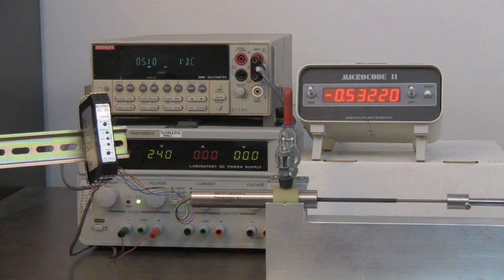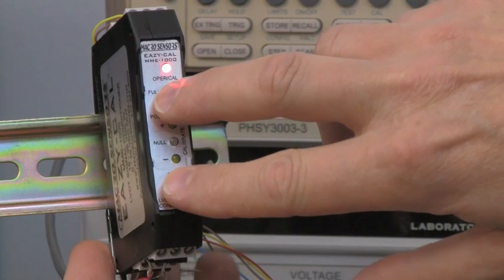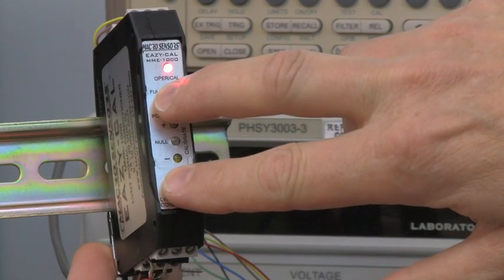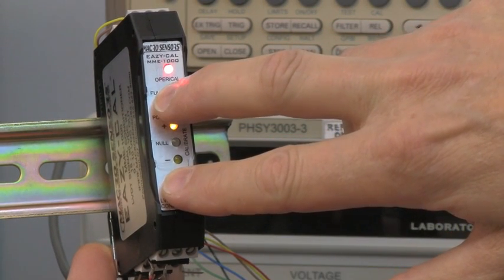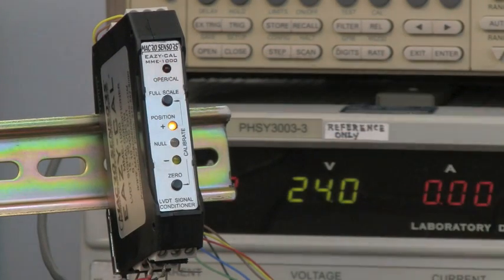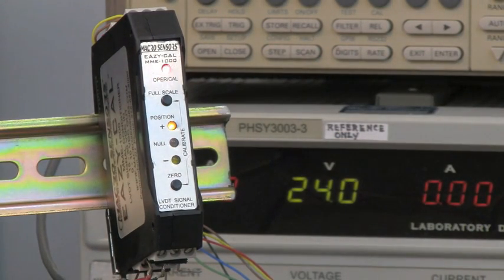With the EAZY-CAL now fully warmed up, we are ready to initiate the calibration procedure. This is accomplished by simultaneously depressing and holding the 0 and full scale buttons for 3 seconds, or until the red OP-CAL LED indicator lamp starts to blink, signifying that the calibration mode has been entered.